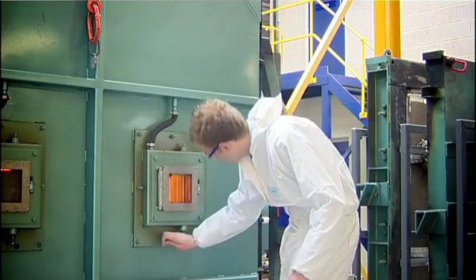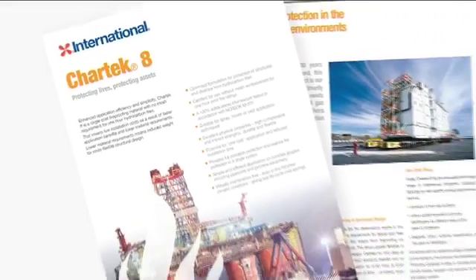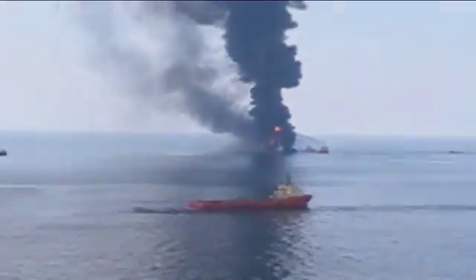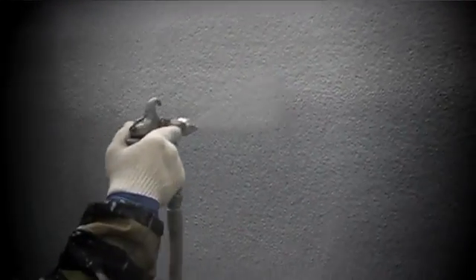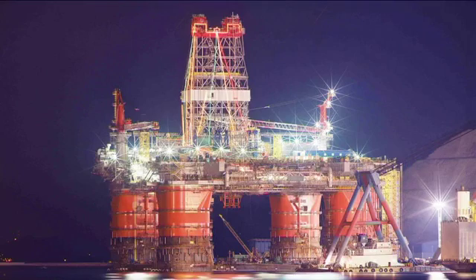In 2004, International's lab in Felling, north-east England, further expanded its furnace capacity. This ongoing investment into the passive fire protection market led to the introduction of Chartek 8. Specifically designed for hydrocarbon pool fires in offshore environments, with improved performance for divisions, Chartek 8 has no mesh requirements for up to one hour and allows applied thicknesses to be minimised, aiding constructability while still providing long-term fire and corrosion protection.